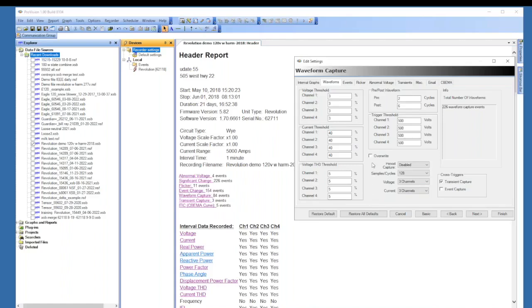Now, if you are setting a recorder and you're leaving it out there for a long time trying to catch an event, then go ahead and leave that overwrite checked. And that way when it hits 200, in this case 227, then it'll overwrite the first waveform capture. But it will hopefully capture the event you're waiting for.